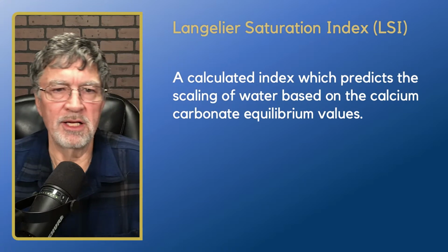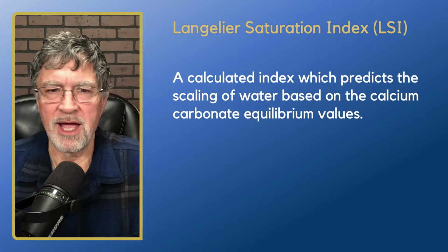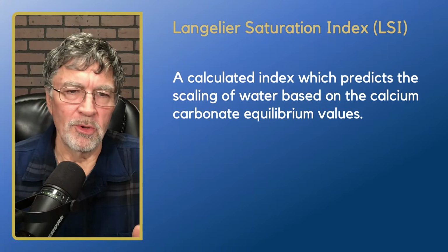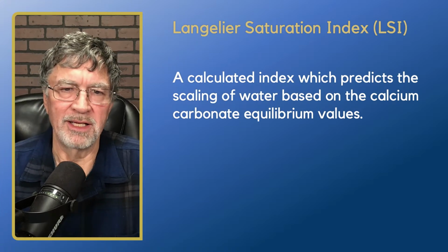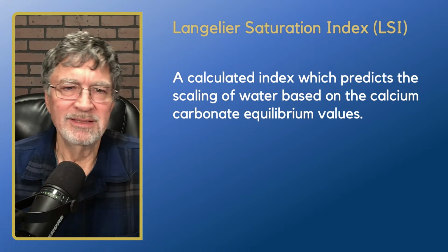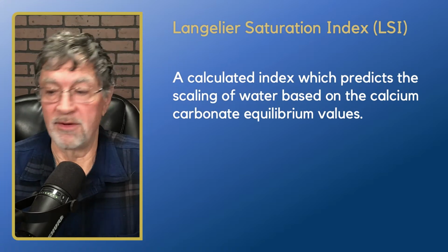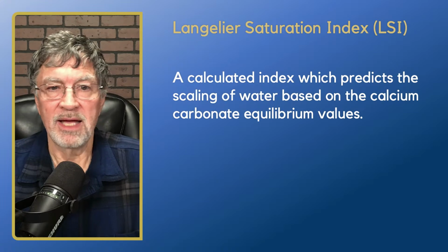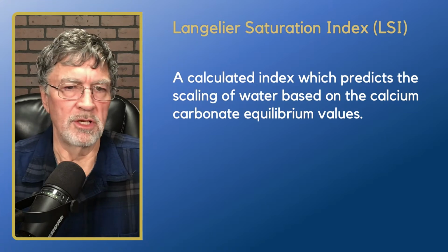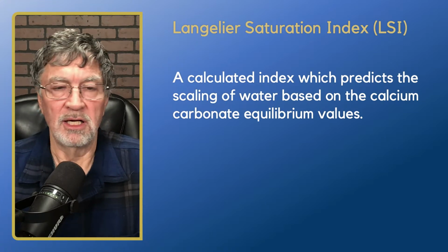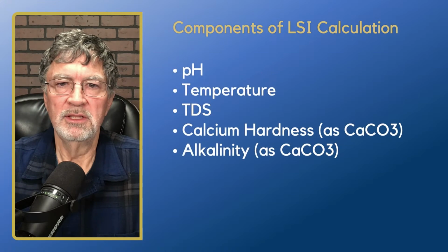If it's undersaturated, the theory with the LSI goes, you have corrosion potential because you don't have that calcium carbonate protective coating on the wells, and corrosion can basically start in bare iron, and so it's supposedly a measure of that. It doesn't quite really work real well for corrosion, but for scaling it definitely is good. And it gives you a good measure, at least for calcium carbonate scaling conditions in a well. That's really one of the most common types of incrustations we see in wells, calcium carbonate. So it is good for that.